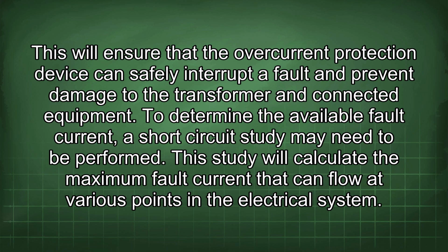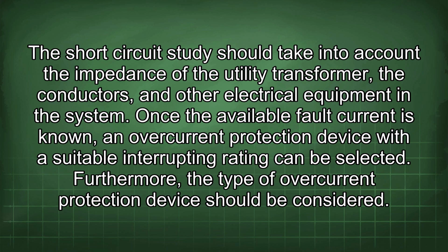This study will calculate the maximum fault current that can flow at various points in the electrical system. The short circuit study should take into account the impedance of the utility transformer, the conductors, and other electrical equipment in the system. Once the available fault current is known, an overcurrent protection device with a suitable interrupting rating can be selected. Furthermore, the type of overcurrent protection device should be considered.